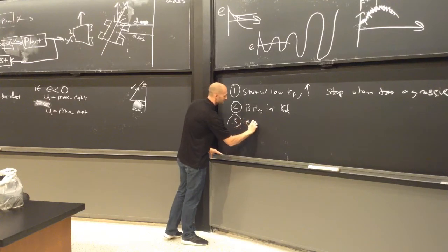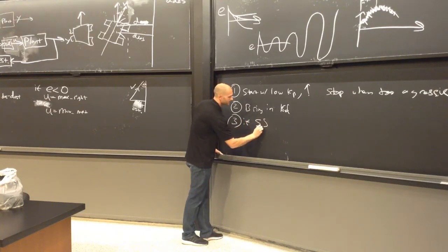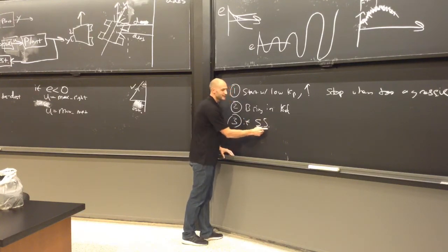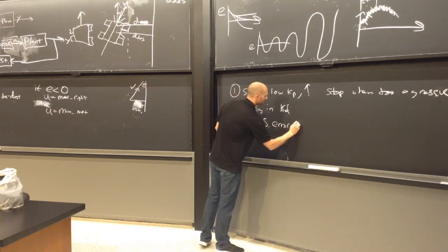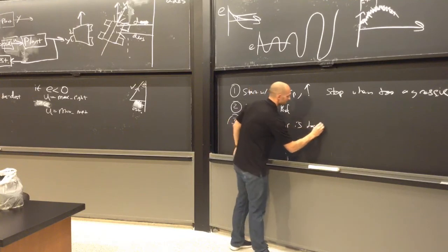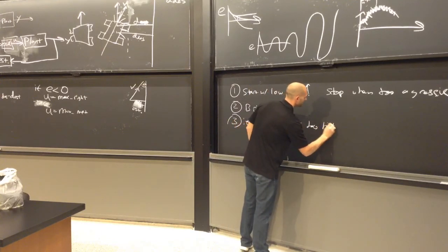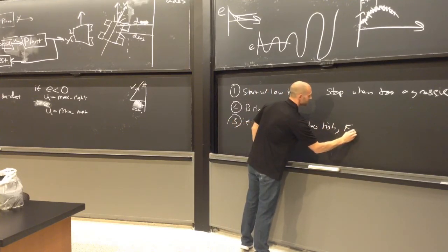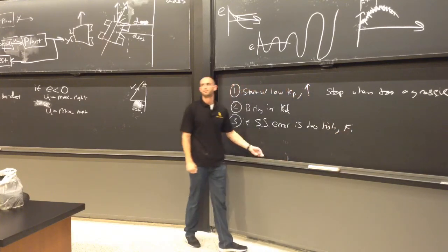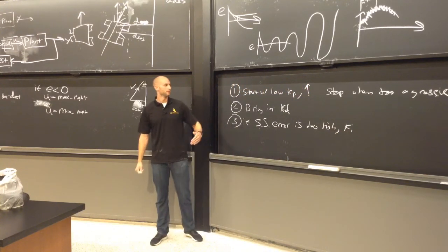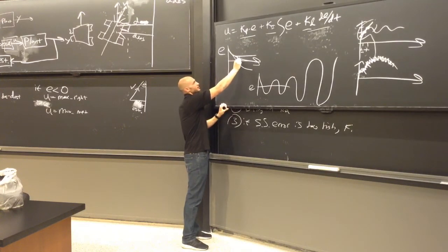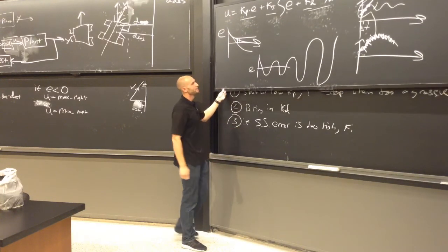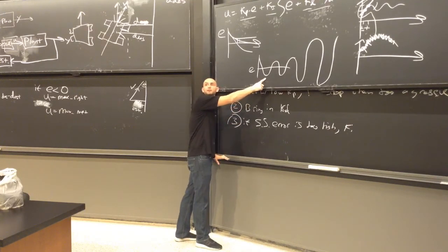And then three, if I'm going to abbreviate here because I'm running out of time. If your steady state (SS) error is too high, then start bringing in the integral term a little bit at a time, and you'll see this effect. You'll see your steady state error start to drop, drop, drop. If you bring in KI too much, you'll go back to this instability.